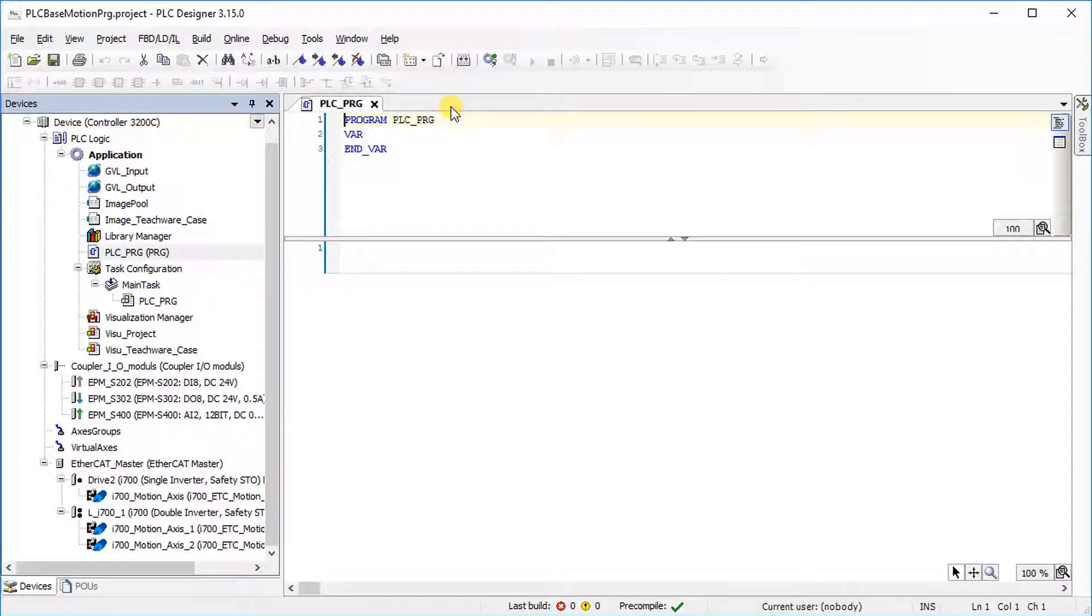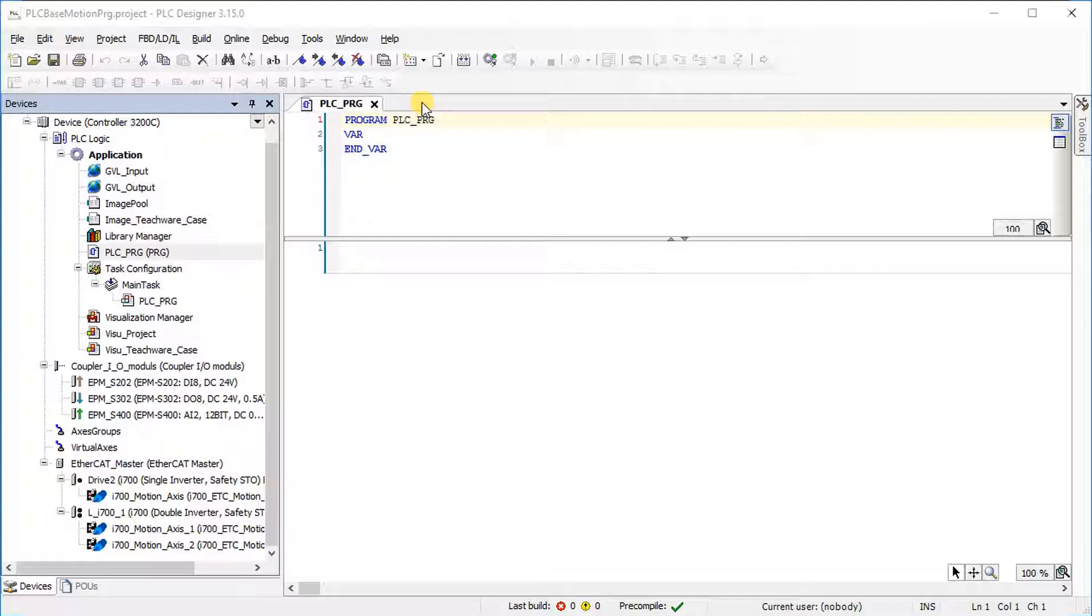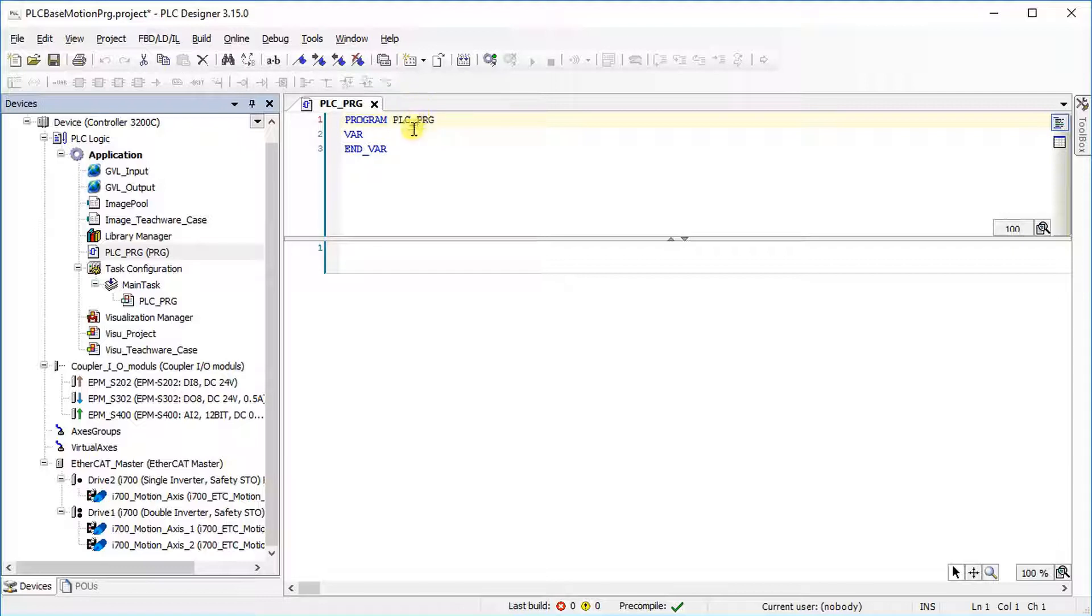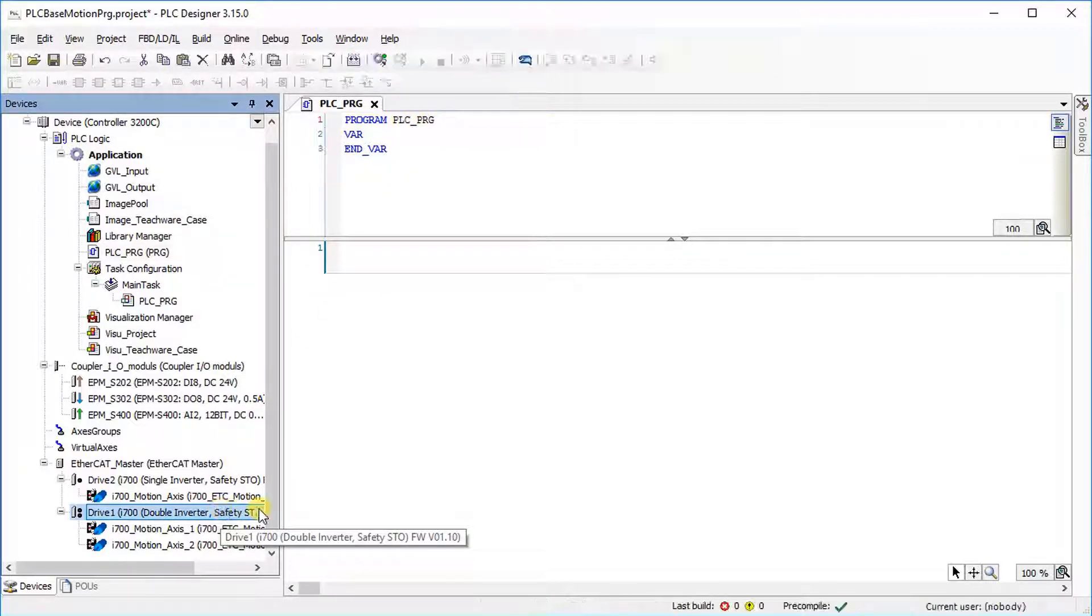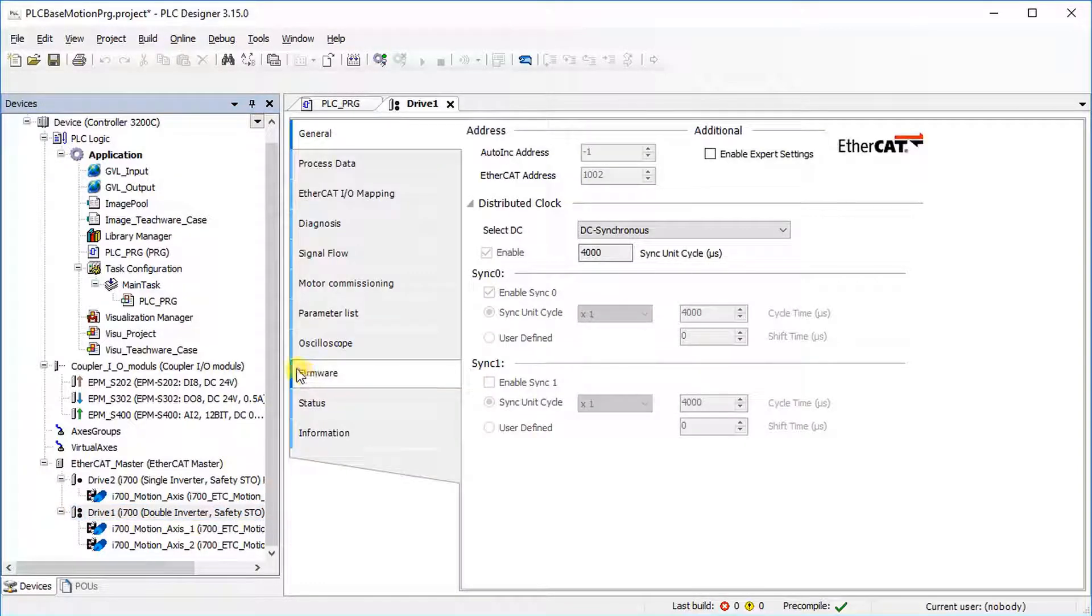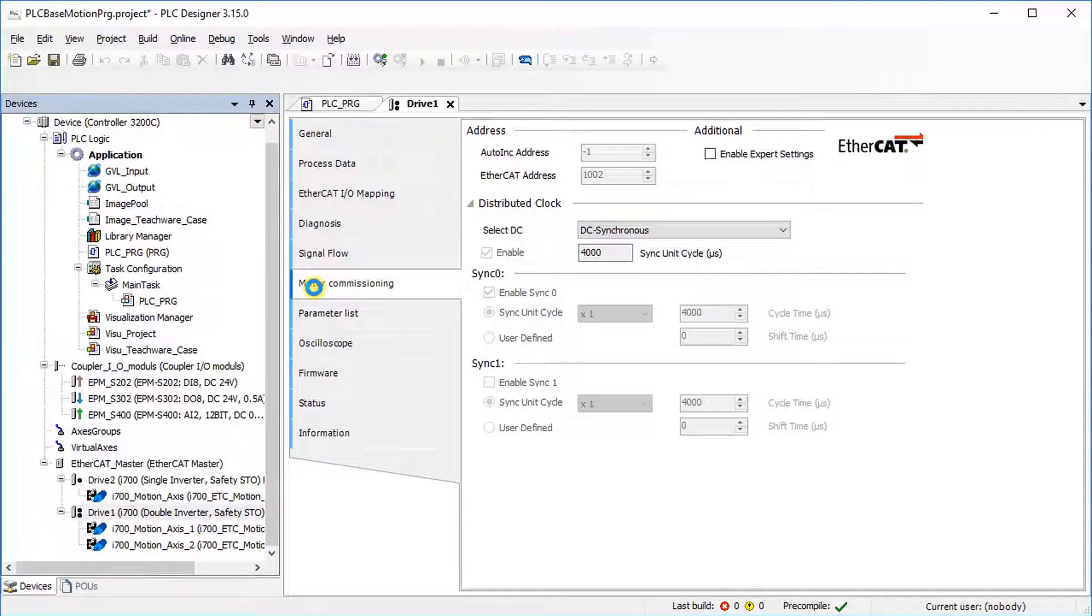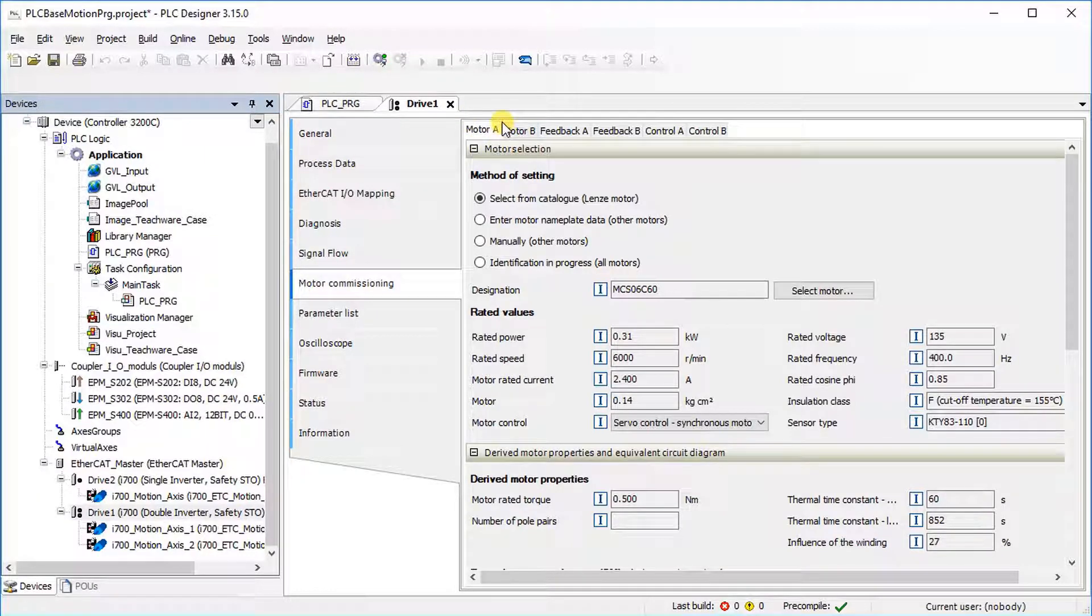Please name the double inverter drive 1 and configure it correctly by following the same procedure as for drive 2. As opposed to drive 2, double inverter drive 1 has two parameter sets for both channels. Right-click on drive 1 and select Edit Object to open the device settings. Under Motor Commissioning, there are separate tabs for setting the motor data, for example, Motor A and Motor B.